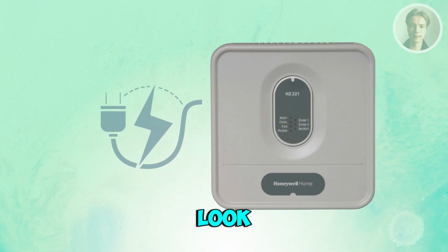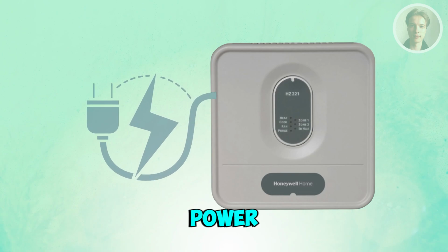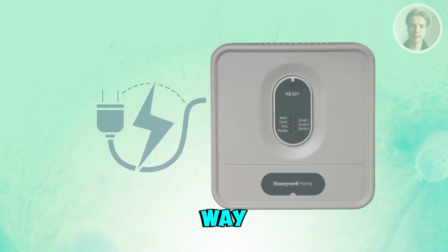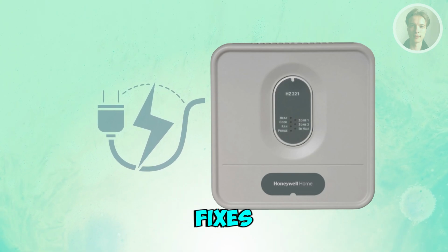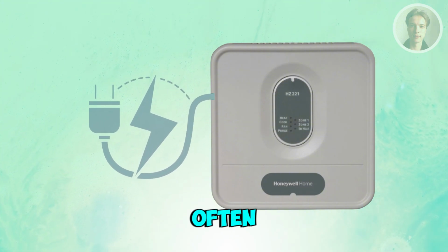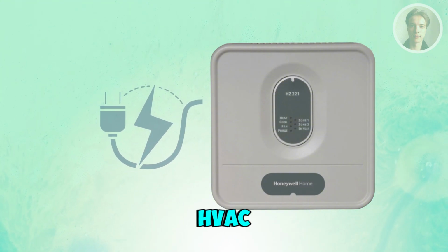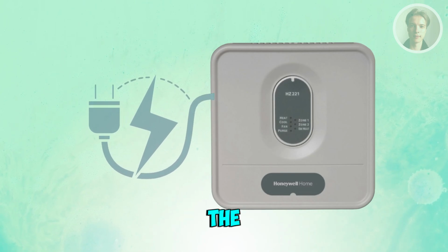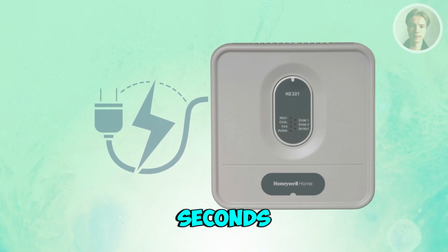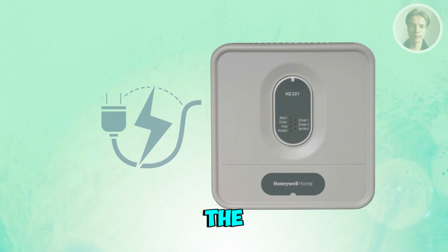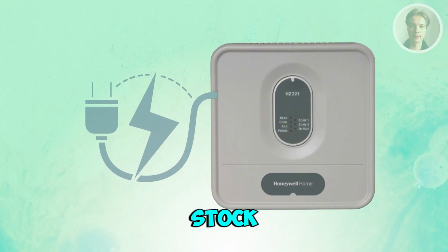Now, you want to just power cycle the panel the correct way. So this is the step that fixes most of the issues most often. So turn off the power to the HVAC system at the breaker, not just the thermostat here. Wait for about 60 seconds, then restore power. Now, this fully resets the TrueZone logic and clears stuck states.